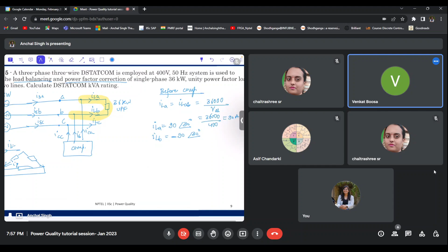So now, after compensation, all the source currents will be balanced. So this will be equal to P by 3 divided by the peak voltage. P by 3, because the total power will divide into all three phases, and when power is divided by voltage, I get the current. This is 36,000 by 3 into Vs peak, which is 400 by root 3. And that is phase voltage. This is phase voltage.